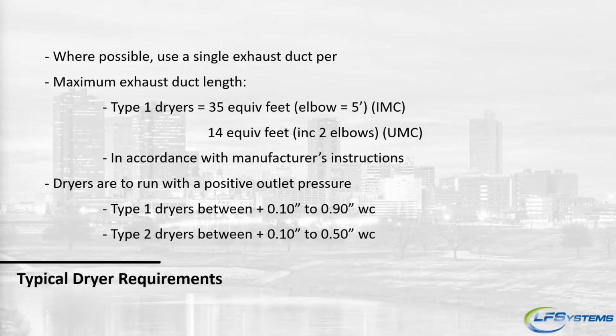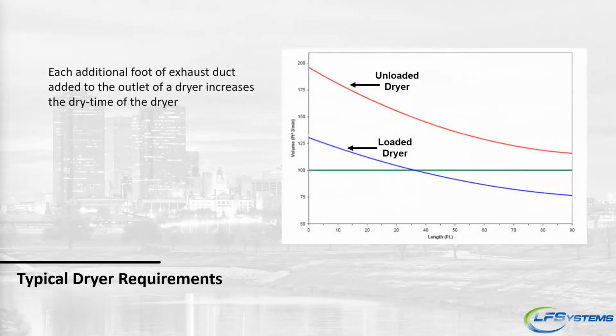of handling that. When you're looking at type 1 dryers, the back pressure, the positive outlet pressure, is typically between 1/10 of an inch and 9/10 of an inch. And that's where this curve comes in: a traditional 200 CFM or 180 CFM residential dryer, that number comes from no back pressure, no pipe attached. So the longer that pipe, or if you add clothing to it, you start to limit the length that dryer can handle. And the difference between, say, a boiler, where if you extend the vent it doesn't operate, the dryer will still operate, it just won't dry.